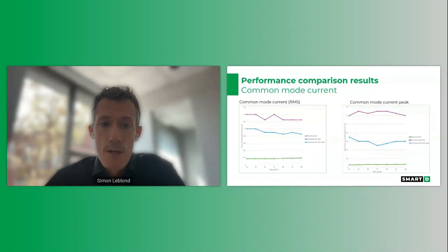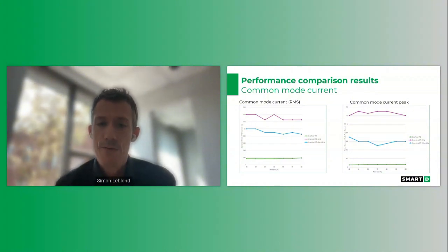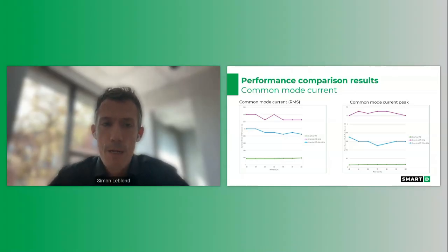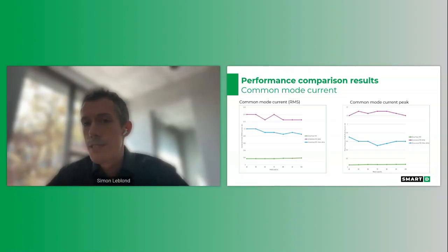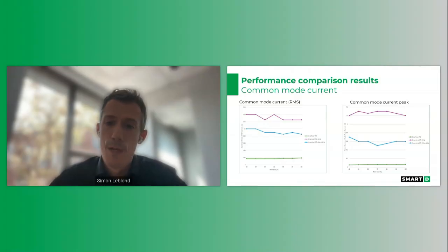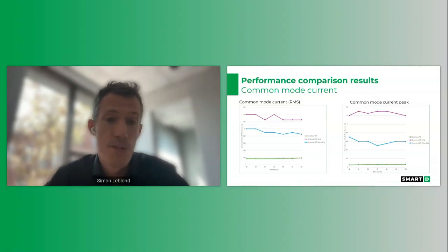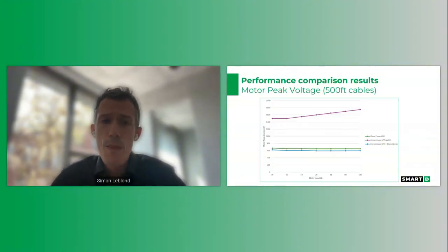So in terms of common mode current, not surprisingly, both on the current and the current peak, it is the conventional VFD that has the worst performance, that pink line at the top of the graph. And we're seeing that if we add the sine wave filter, we are helping the result. So we are decreasing both the common mode current and the common mode current peaks. But it's really the Clean Power VFD that's outperforming everything here, with virtually no common mode current getting through, a very, very low value. So this is something where the Clean Power VFD can offer benefits that, yes, are somewhat mitigated by filters, but not completely.